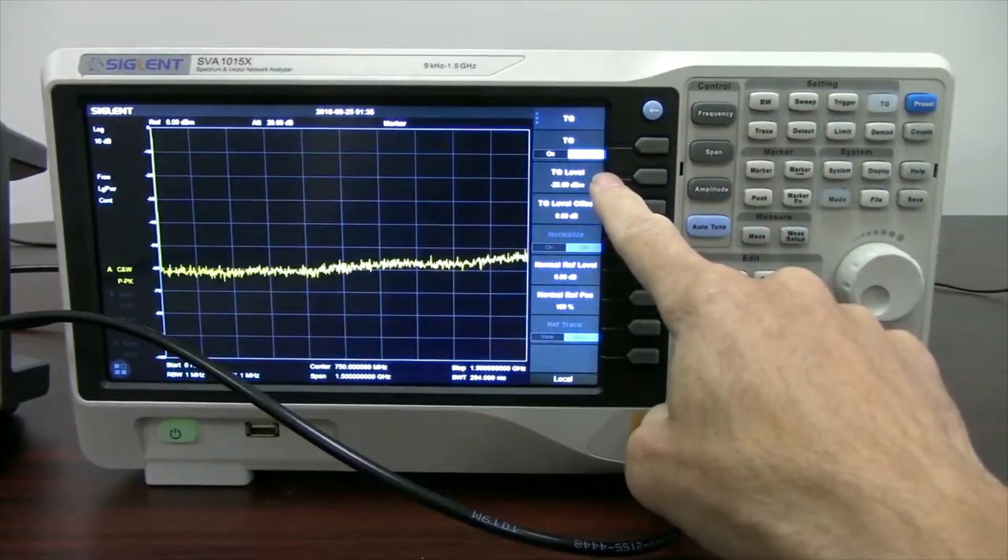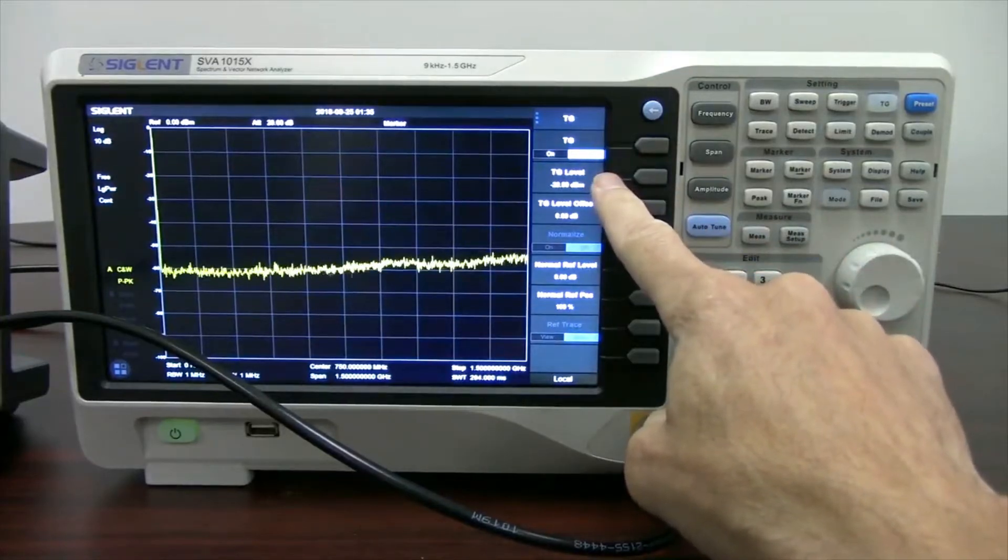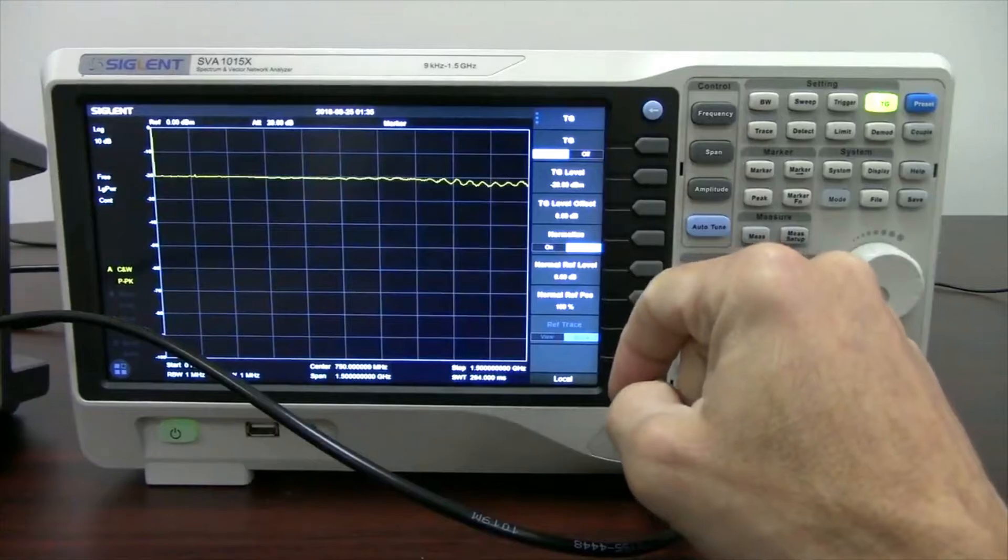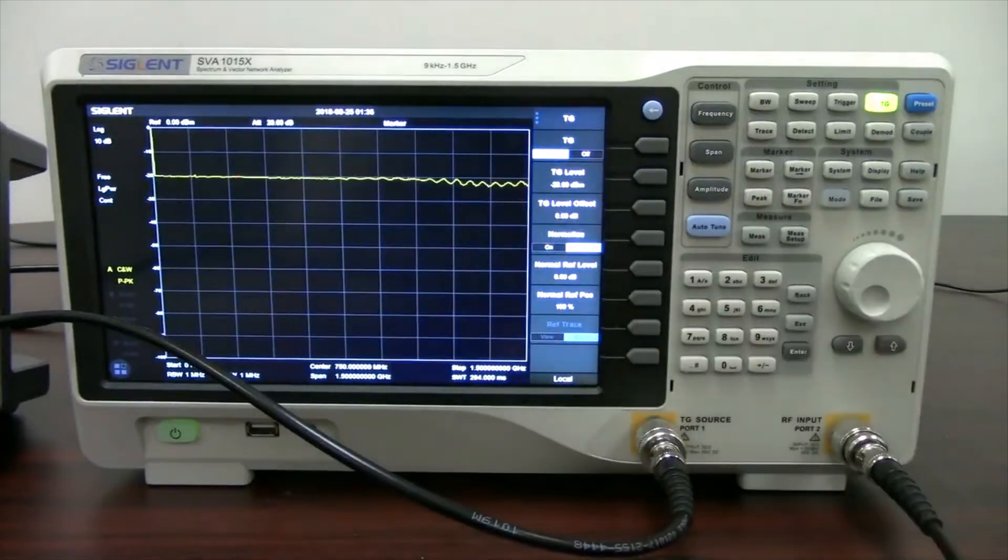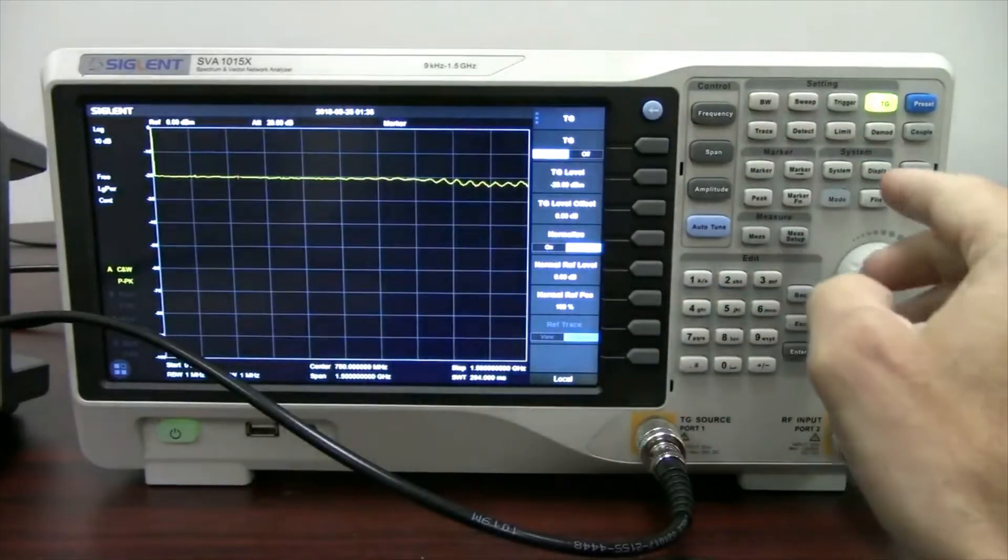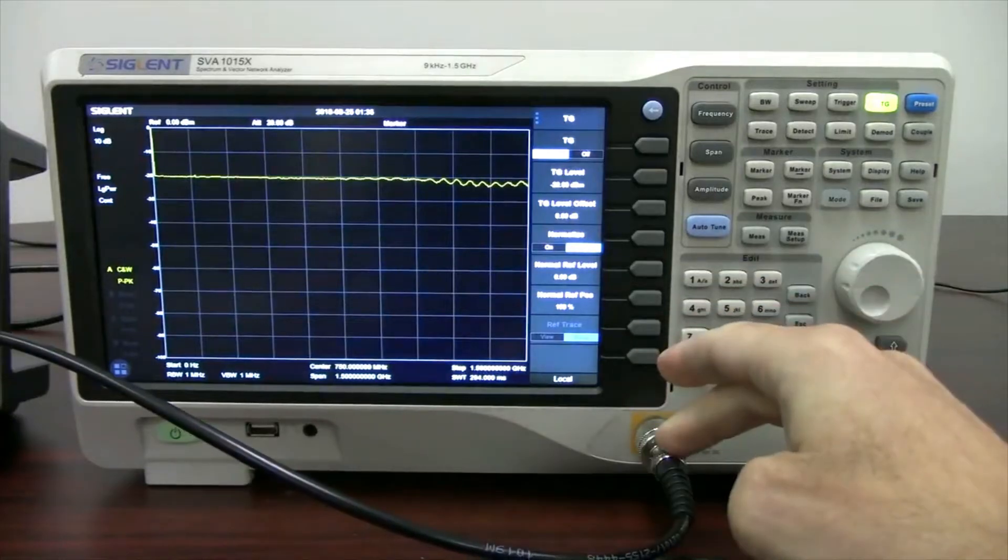And you'll see that the tracking generator level is set to minus 20 dBm. So when we turn on the tracking generator, lo and behold, we've got a line right here coming across about minus 20 dBm. A lot of the ripples and things that you see are totally normal, they're within specifications. Some of them are due to cable effects, as well as the adapters.